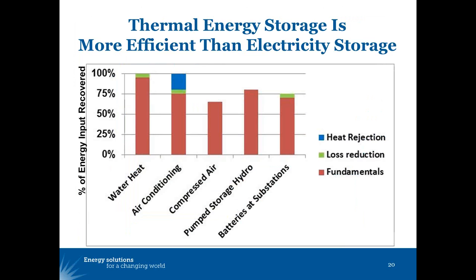And in terms of thermodynamic efficiency, some of the studies on air conditioning storage by ICE Energy, a company that makes systems designed for the kinds of air conditioners put on strip malls, are showing more than 100% efficiency. That is, the gain in efficiency from doing the heat rejection at night outweighs the energy loss from first turning water into ice and then turning ice back into chilled air. I put this at 100% efficiency, but ICE Energy is claiming about 110% net efficiency - that is, the heat rejection gains and the loss reductions.